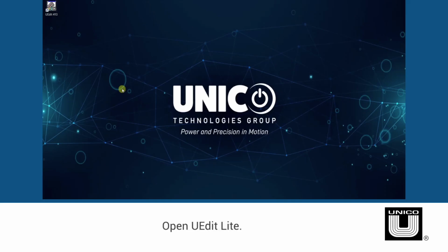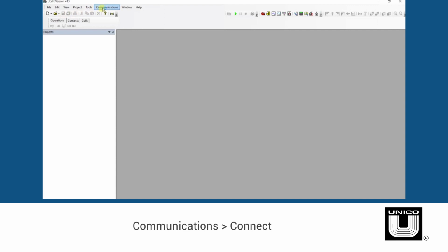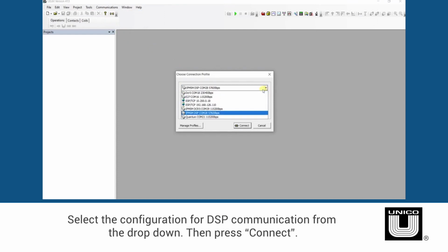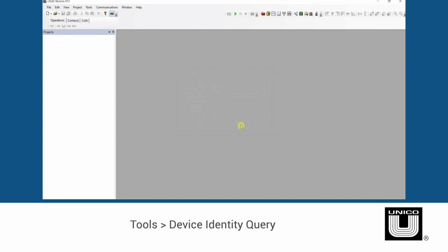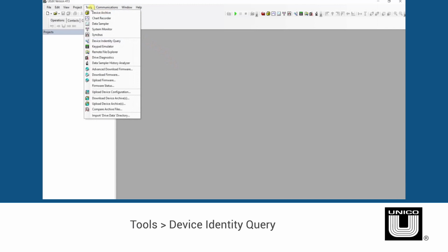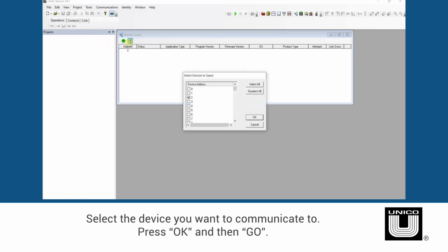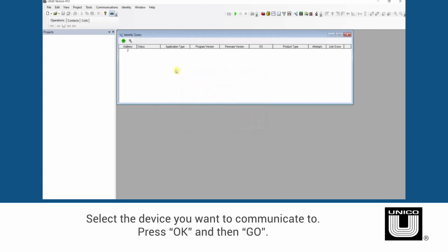Once the physical connections to the DSP and DCR5 module have been made, make sure there is communication to the modules via UEdit. To do this, open an instance of UEdit. Go to Communications, Connect, and select the configuration for the DSP communication. Then go to Tools, Device Identity Query, and select the device you want to communicate to. For this example, I will be communicating with device 2, which is the drive for the IPM motor. Then select Go and ensure you have communication.